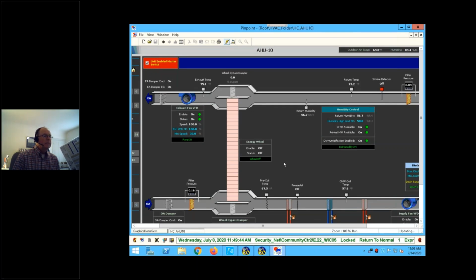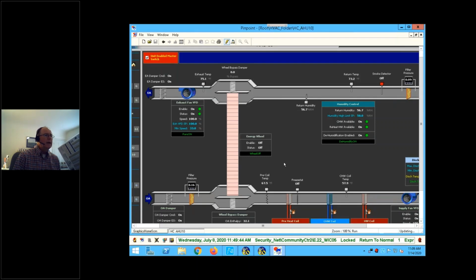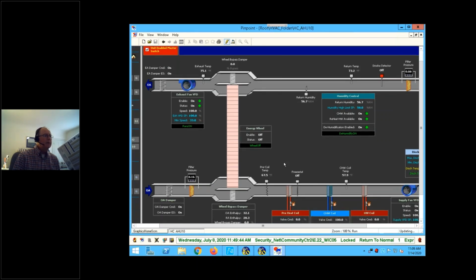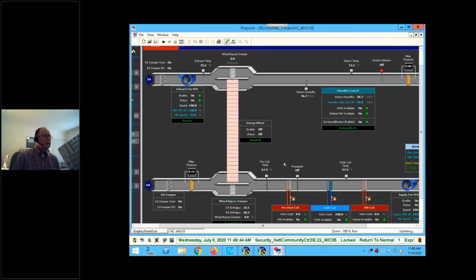Okay, I wonder if that's reasonable. Do you always go through the wheel when we have bypass dampers? Well, we would only do that in the event that we're not economizing and it doesn't seem advantageous to use the wheel. So there's a series of conditions that would turn the wheel on and off based on whether they want heat or cool reclaim, and another series of conditions for whether we're going to want to economize.